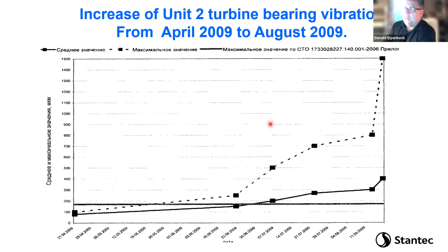Okay, but the units were still running. Now, this shows what was going on just seconds prior to the accident. And you can see a couple of interesting things here. First, I circled the amplitude of the vibration. Unit 2 is at 840. The next closest is at 200. Some of these are down at 50, and those were really low power. So there were a lot of signs that things were going wrong.